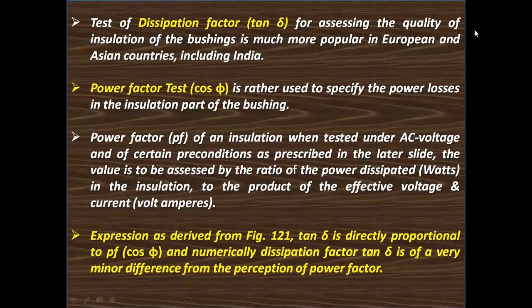Test of dissipation factor, that is tan delta, for assessing the quality of insulation of the bushing is much more popular in European and Asian countries, including India. But the power factor test, cos phi, is rather used to specify the power losses in the insulation part of the bushing. Power factor of an insulation is tested under AC voltage and certain conditions as prescribed in the later slide. The value is assessed by the ratio of the power dissipated, that is watts, in the insulation, to the product of the effective voltage and current, volt amperes.